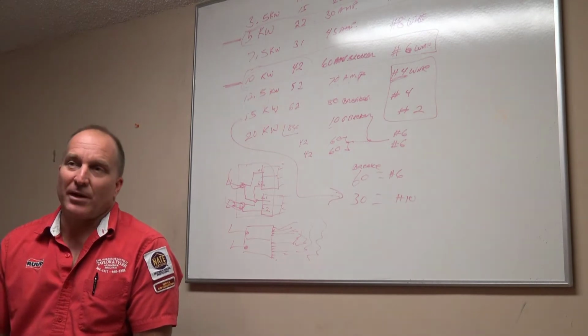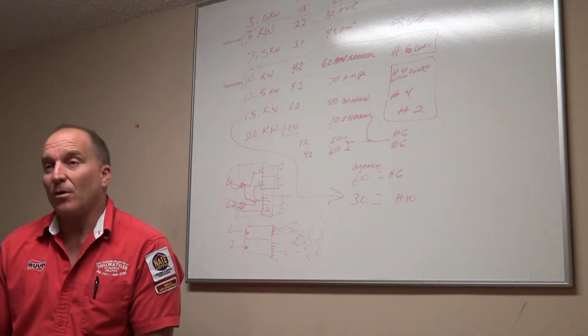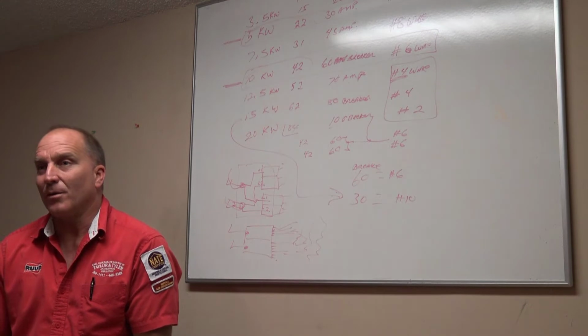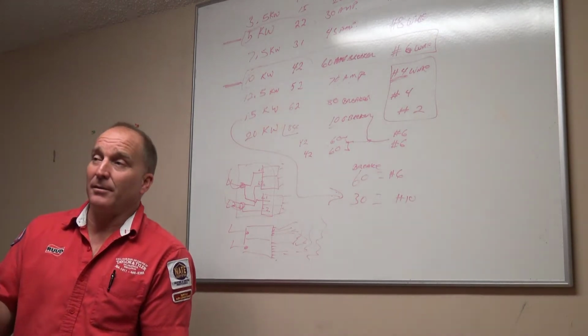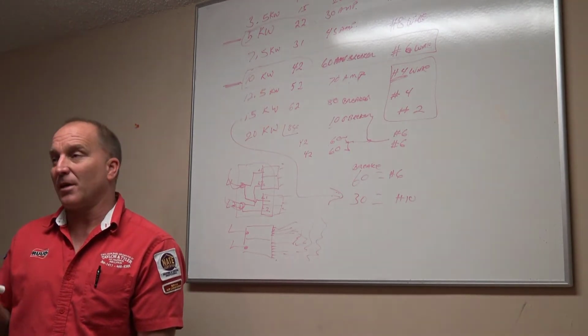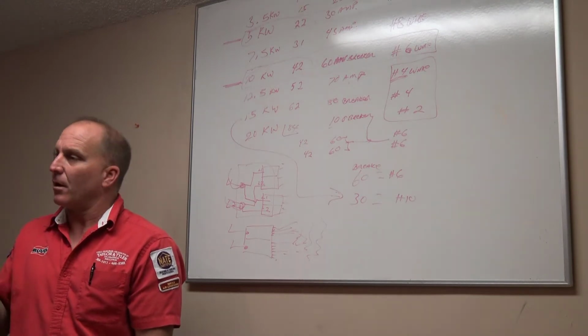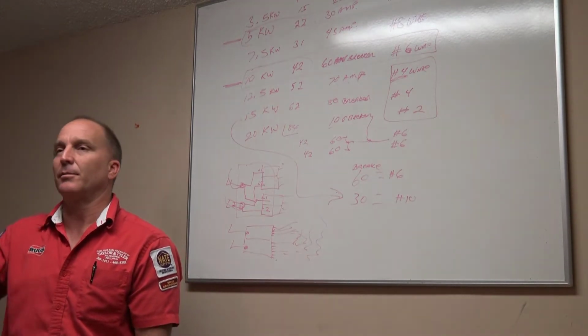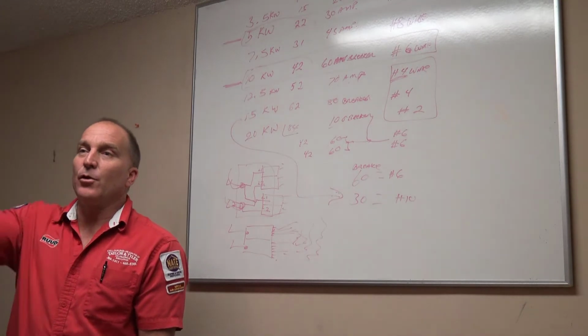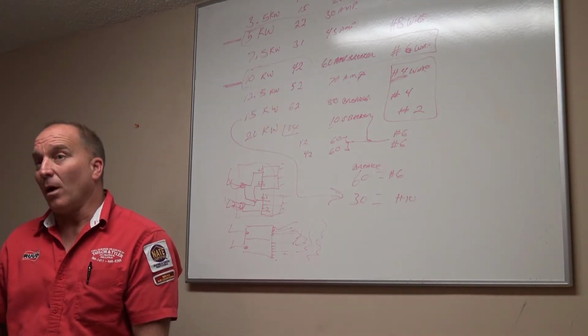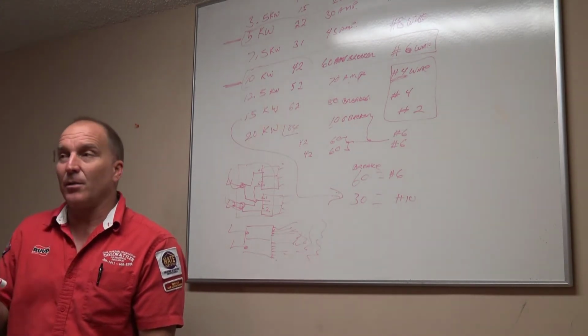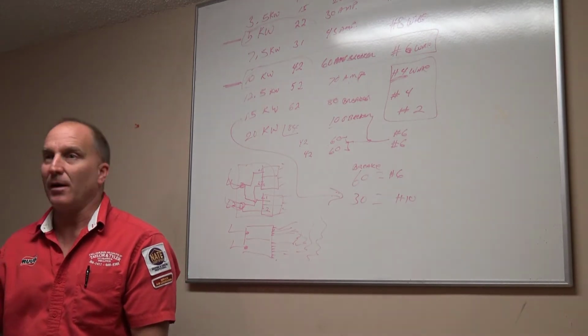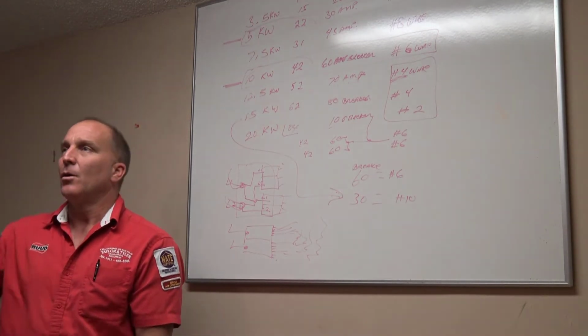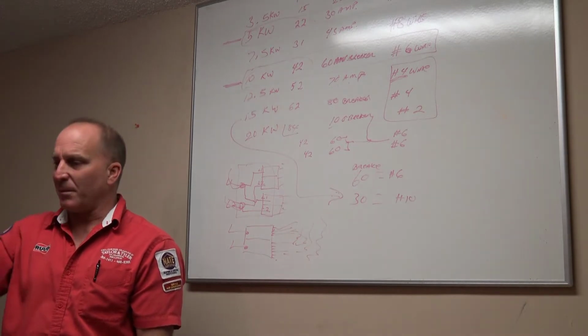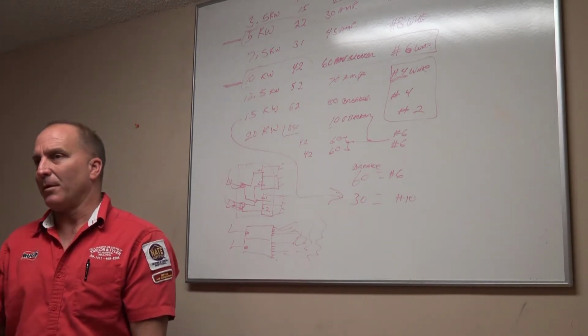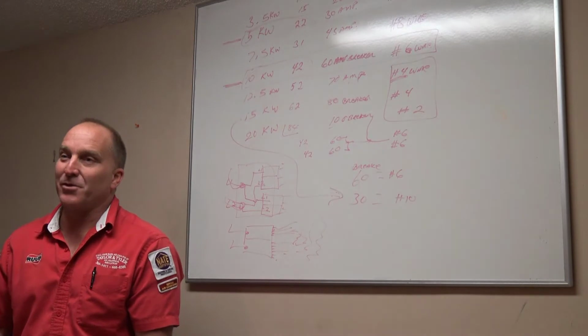We just got finished with a video on gas furnaces. I think I can draw how all my wires go because I know where they're going, right? If you got a 16-pin plug, all your safety devices and everything are going into a plug. Oh, I guess it goes into the 16-pin plug. Okay. Well, you take your 2 wires and go to your IDM motor, and one of them is going to the IDM motor, and the other one goes to a neutral. All right, that's fine. I can figure that one out. Okay. Orange wire from the flame sensor. Well, I'm going to bring that to the one that says flame sensor on the circuit board.